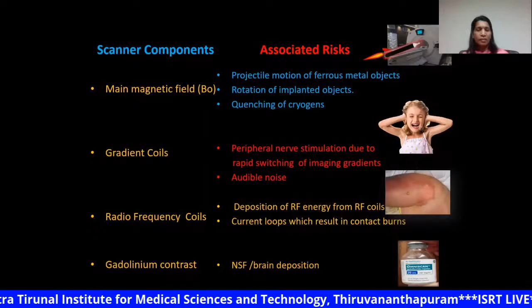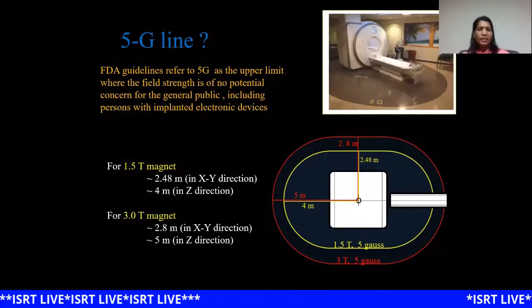So these we will see each separately. The magnetic field, if we consider, is not limited to the bore. It extends outwards, and we call this the fringe field. As the distance from the magnet increases, the field strength, that is the fringe field, decreases. The FDA considers the 5 Gauss line the safe limit, outside which the magnetic field will not affect patients with implants or other electronic devices. It doesn't mean that we can bring ferromagnetic material up to the 5 Gauss line.